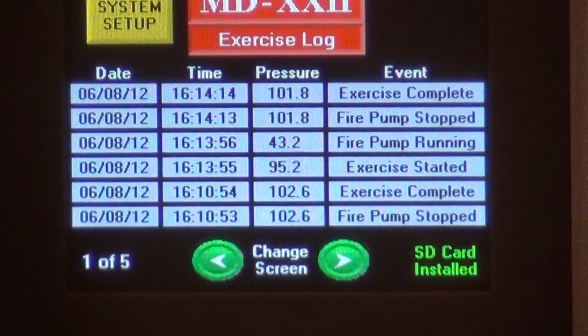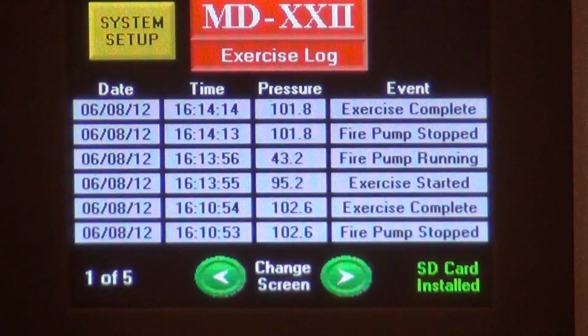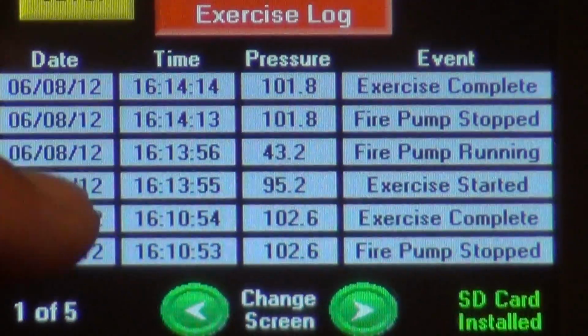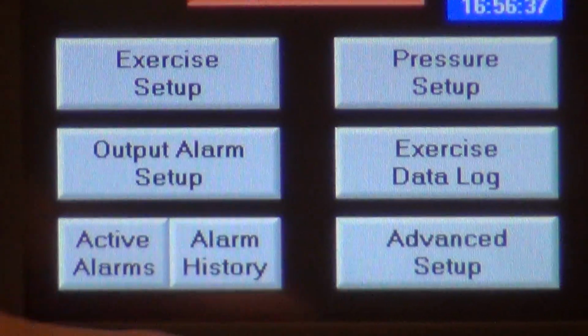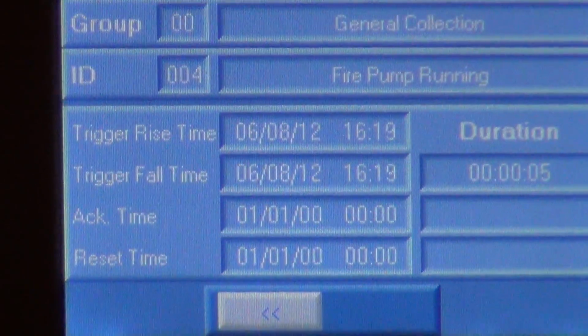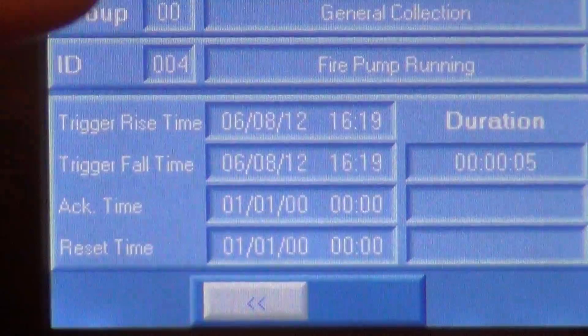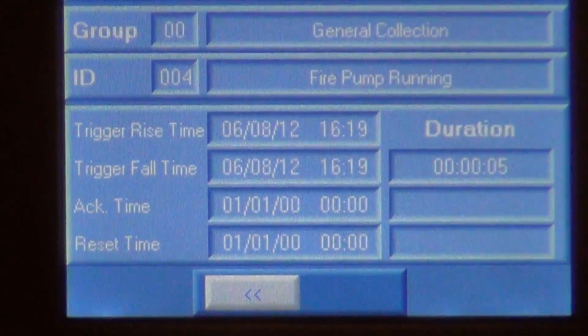For example, your insurance company would like to see how often you're exercising your system. It would show you when your exercise began, your fire pump running, your fire pump stopped, and your exercise is complete. An alarm history can be displayed by simply going into the alarm history screen.